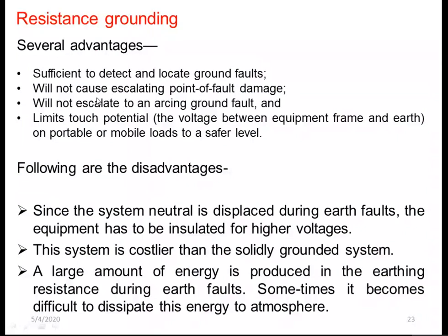Then there may not be any arcing ground fault, because if you refer to the ungrounded system, because of the charging and discharging of the phase capacitor, there is arcing occurrence, and thus in the case of resistance grounding, this can be eliminated.